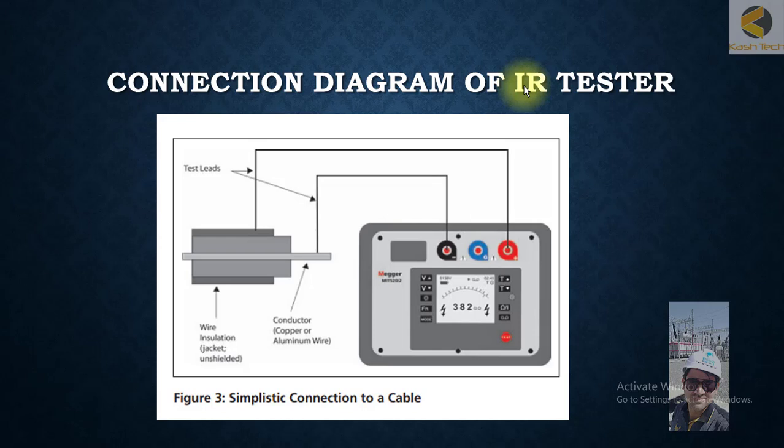Now you will see the connection diagram to test a simplified cable which doesn't have a metallic sheath. You are connecting the object under test—the cable connector—to the negative lead for the insulation testing equipment. You will connect the insulation to the red lead, so in this way you can test the insulation for the cable.